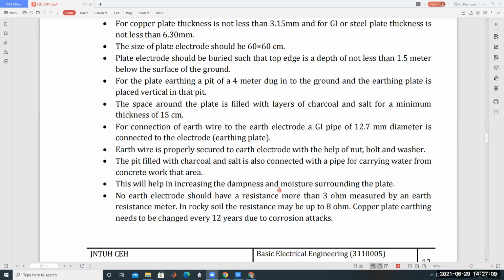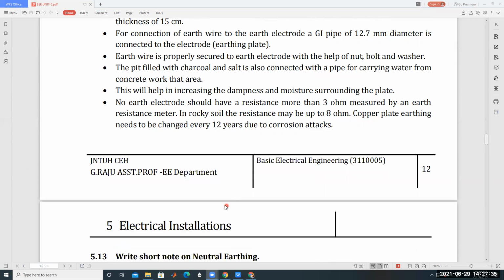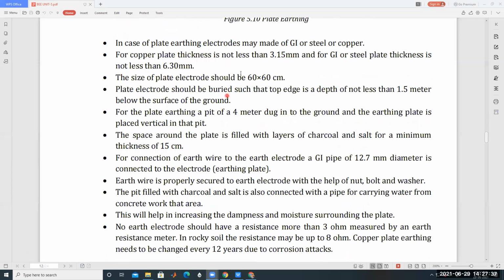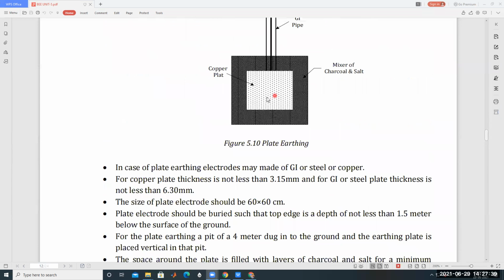No earth electrode should have a resistance of more than 3 ohms, measured by an earth resistance meter. In rocky soil, the resistance may be up to 8 ohms. Copper plate earthing needs to be changed every 12 years due to corrosion attacks. So this is about plate earthing and pipe earthing. This is called plate earthing.